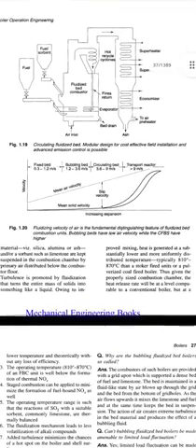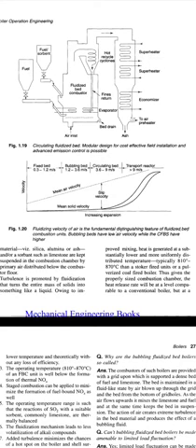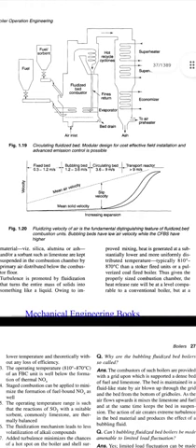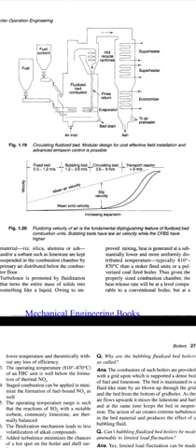The next diagram shows fluidizing velocity of air. The graph shows velocity and increasing expansion. Fluidizing velocity of air is the fundamental distinguishing feature of fluidized bed combustion units. Bubbling beds have low air velocity while the CFBCs have higher.